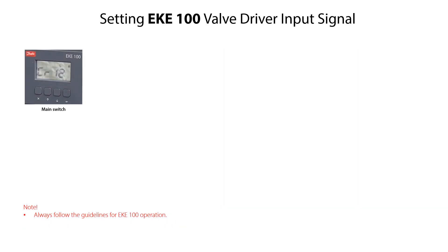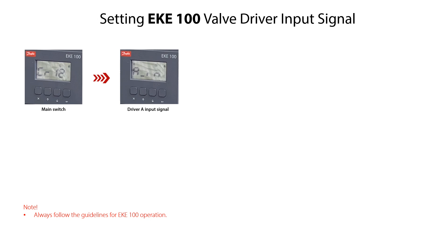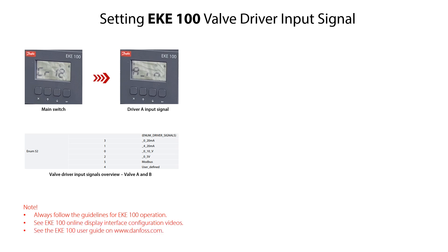To configure the EKE100 valve driver input signal for valve A, from the main switch CR12 mode, press the arrow down key several times to access the driver A input signal, specified as AIN. Press the enter key to access the available input signals. You can see the different values and corresponding input signals in the overview shown here. Press the arrow up or arrow down keys to get the needed value, then press the enter key to confirm the value and return to the AIN mode. Once set, press the arrow up key to return to the main switch CR12 mode.